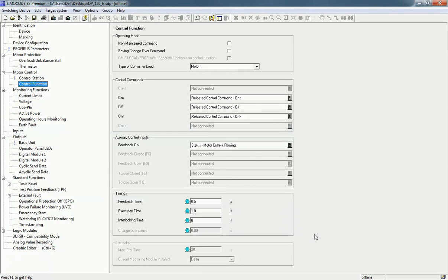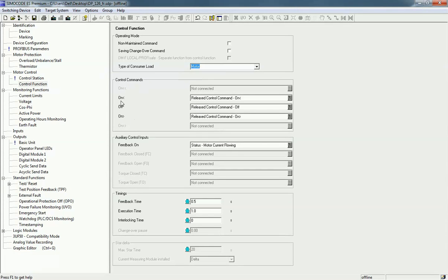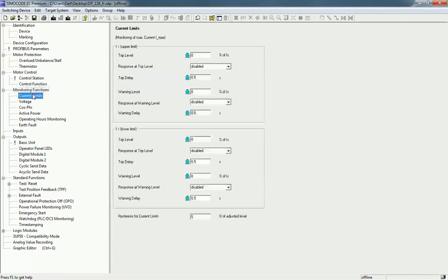Next is the Control Function section. Here you can define feedback time, execution time, and interlocking time. You can also select the type of consumer load — resistive or motor load. For control commands, when the motor turns on, it releases a control command for reverse on; when the motor is off, it releases the command for off; and when running in the forward direction, it releases the command for on. From these release control commands, you can go to the next controlling level, which we will see in the next video.